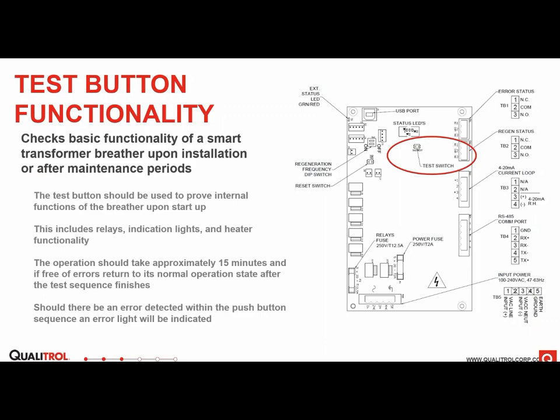And when you press the test button, you can let it sit. You'll hear the relays click on. You can actually test all of the relays too. They will all close. And if you let it sit, you'll be able to actually feel the heater heating up. It takes about 15 minutes to feel that. So that's a nice feature to make sure that the breather is functioning as it should.